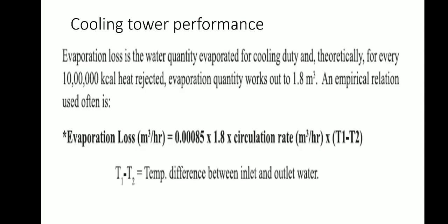Then next, evaporation loss is the water quantity evaporated for cooling duty. Theoretically, for every 10 lakh (1000000) kilocalories of heat rejected, the evaporation quantity works out to 1.8 meter cube. An empirical relation often used gives the evaporation loss in meter cube per hour during cooling operation.